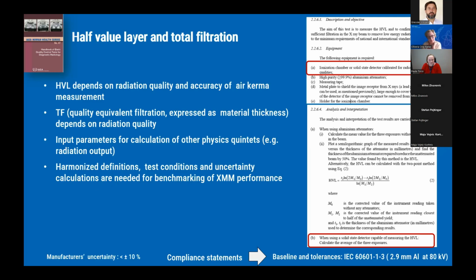I'm not quite sure that half-value layer should be considered as a physical quantity because it's not directly measured. It's rather calculated based on the air Kerma measurements and thickness of aluminum, which means that HVL heavily depends on radiation quality and accuracy of the air Kerma measurements, and pretty much the same applies to the total filtration. These two parameters are quite important because they're also input parameters for calculation of other physical quantities, for example, radiation output or mean glandular dose in mammography, which is why we need harmonized definitions and well-defined test conditions to assess uncertainty associated with assessment of the HVL in clinical conditions.